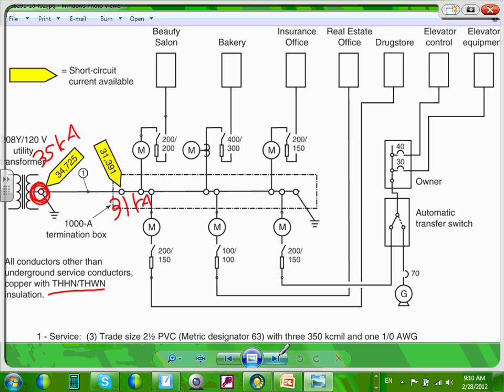So if I ask you, Nick, my friend, can you please do me a favor and do the calculation right in this? Would you expect the short circuit right here to be higher than 31 or lower? If you write in your resume that you know how to do short circuit calculation, and you come interview with me, and I say at the service you have a short circuit of 31,000, and I move say 100 feet to a downstream panel, would that short circuit be higher than 31 or lower? It would be lower. The impedance chokes the current.